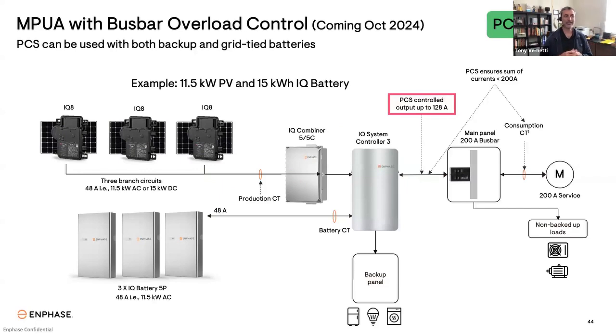Now let's take a look at an example of Busbar PCS on a system with backup capabilities. The system has an IQ system controller, so it can disconnect from the grid and provide backup power. So in this example, now we have a 200 amp service and 200 amp main panel, bus, and breaker. With today's version of PCS, the backfeed limit would be 32 amps on a typical 200 amp panel. So this example with an 11.5 kilowatt PV system wouldn't be able to produce its max power at all times.